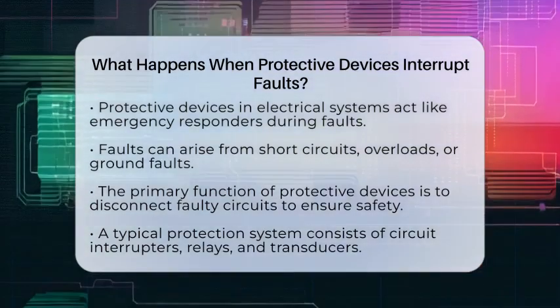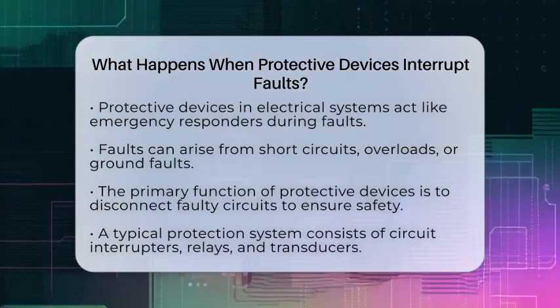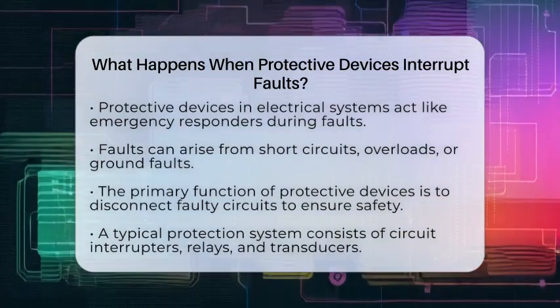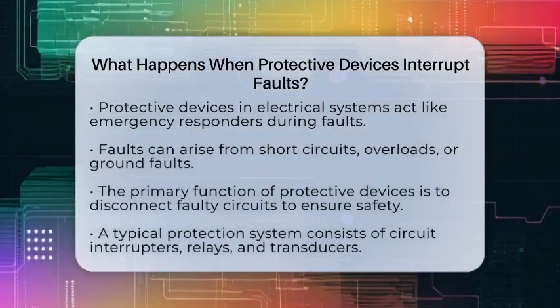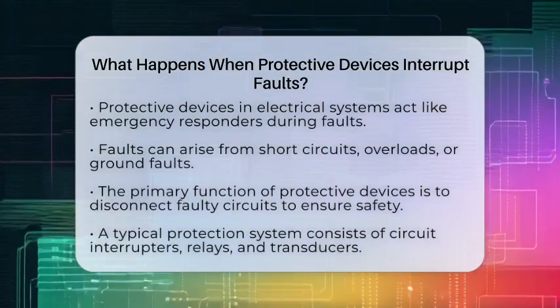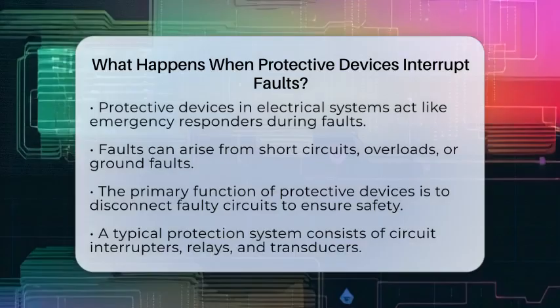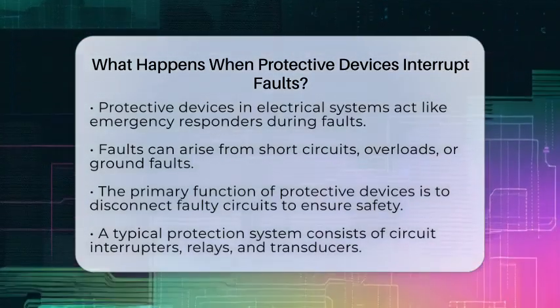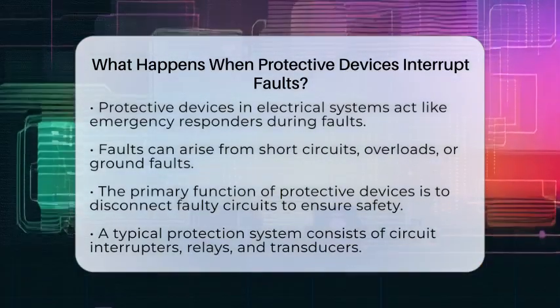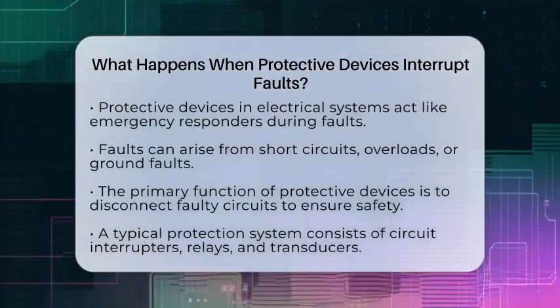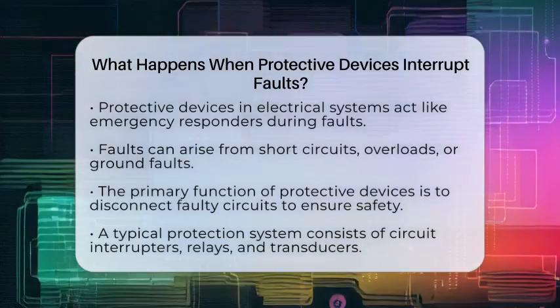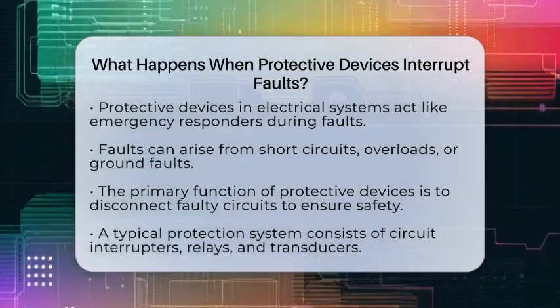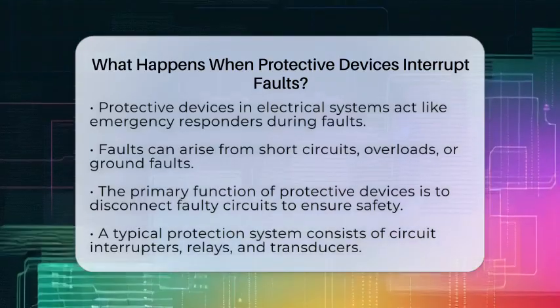The main job of protective devices is to detect these issues and disconnect the faulty circuit from the rest of the system, ensuring safety and preventing damage. A typical protection system includes three key components: circuit interrupters, relays, and transducers. Circuit interrupters are devices designed to break the circuit when a fault is detected. Common types include fuses and circuit breakers.